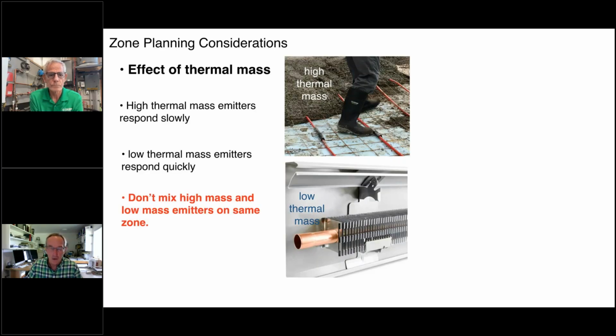Think about turning an ocean liner with an oar as an example. Eventually you could do it, but it's a very slow process. Versus a low thermal mass heat emitter like a fin tube baseboard or a panel radiator or a fan coil. They respond very quickly. And it makes sense that you don't want to combine a high thermal mass heat emitter with a low thermal mass emitter on the same zone, because the low mass emitter is going to reach a temperature much faster than the high thermal mass. So in general, you want to separate those based on thermal mass.